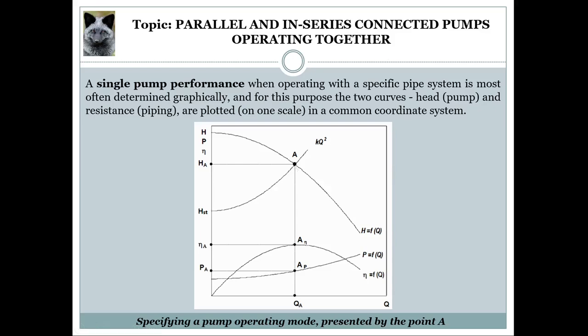Point A is known as the pump operating point and is used to specify the values of the pump operating parameters, such as pump flow rate presented by QA, pump head presented by HA, pump input power presented by PA, and the pump coefficient of efficiency presented by eta A. For a particular pump and relevant pipe system, there is only one operating point, meaning there will be just one flow rate — in this case QA — that can be ensured by the system.